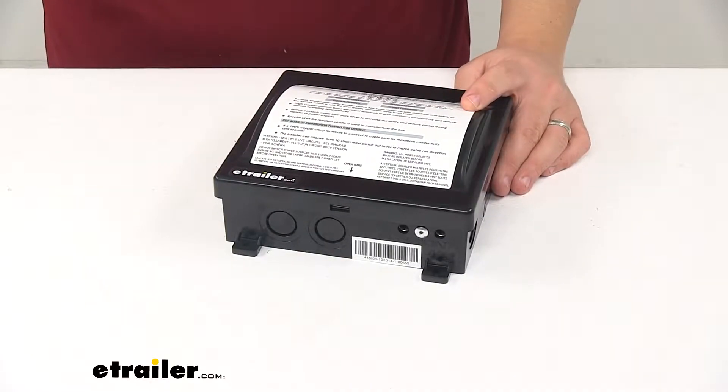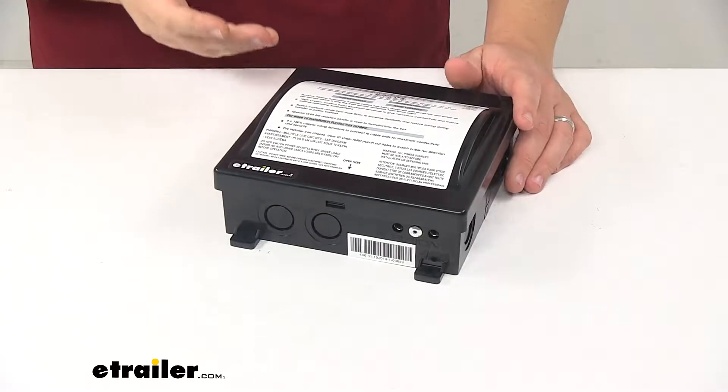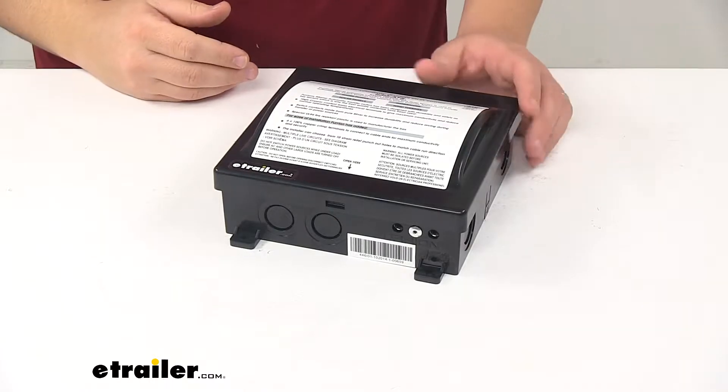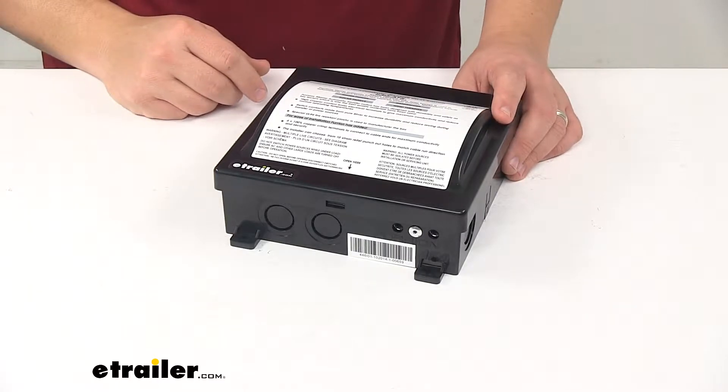Today we're taking a look at the Furrion Automatic Transfer Switch. This is a 30 amp transfer switch, and what it does is it transfers automatically between two separate 120 volt AC power sources, such as shore power and generator or inverter electrical feeds.